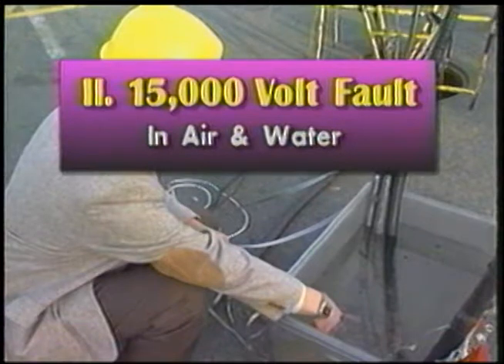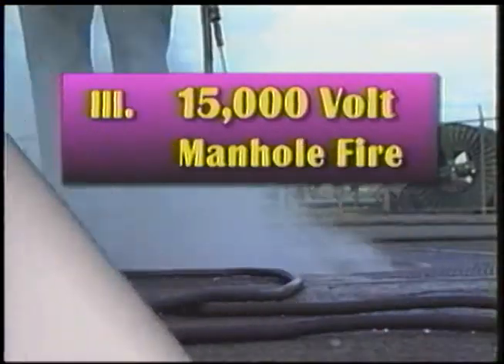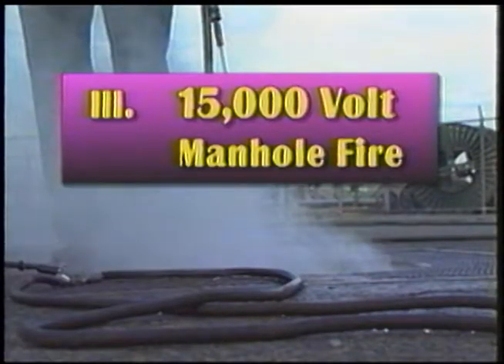We'll measure some voltages to show you that it's safe to make contact with the water when there's an electrical fault in the manhole. The last demonstration we're going to do is a 15,000 volt fault in the manhole, in which the electrical fault will set the manhole on fire. While the fault is there and the fire is burning, we will put the fire out with the hose.